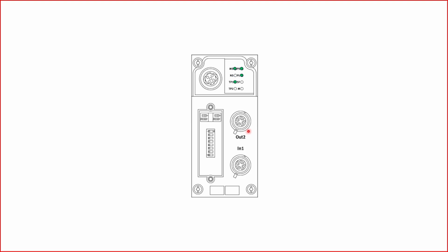If you have a solid LED light on the manual or modify LED, this means that the settings have been saved inside the CPX itself, meaning that possibly the IP address could have been changed or any of the additional safety requirements were changed.